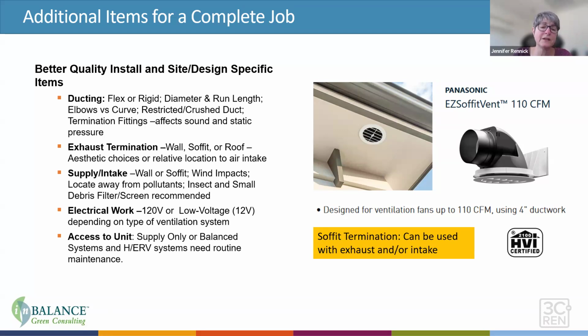But the one thing that you may be interested in as an architect, that you do have some control over, is how that exhaust termination is going to look and where it's located. So you want it away from your dryer exhaust, for example. And you want the supply intake away from the other, I think I misstated that, sorry. You want the supply intake away from the dryer exhaust, and you also want the supply intake away from the exhaust on the system. And then probably the last thing to really think about is the accessibility to the unit itself, because the balanced systems and the supply only systems do have filters, and it makes a big difference if the owner or whoever's doing the maintenance can access those and change the filters.